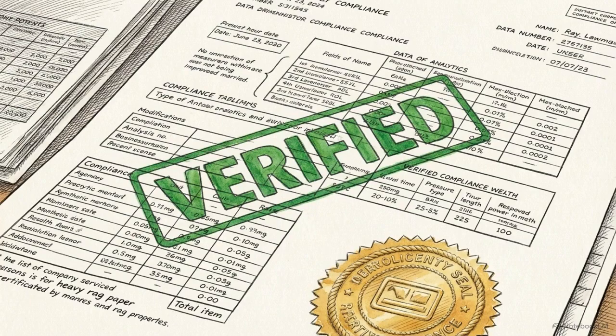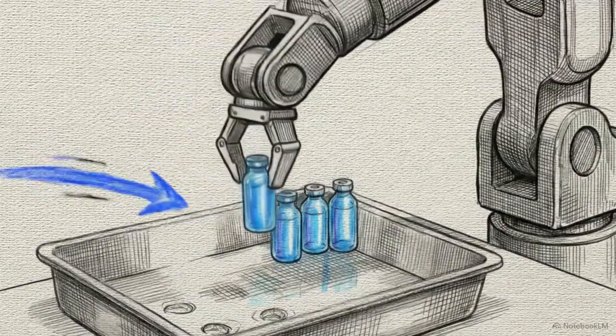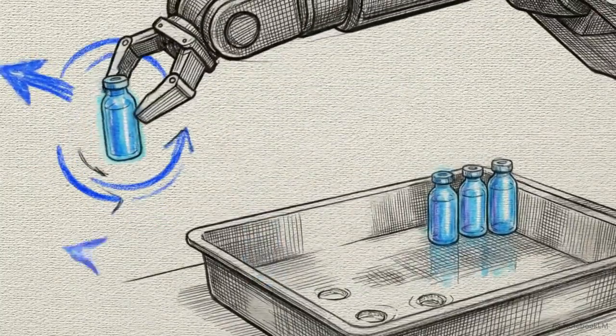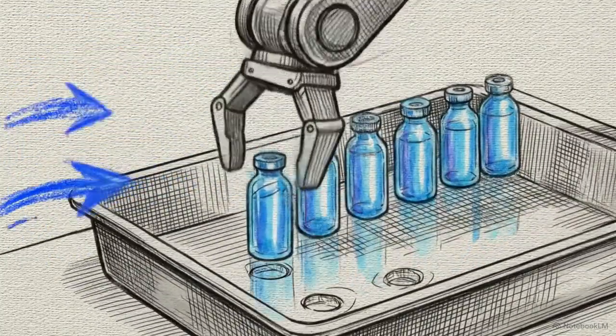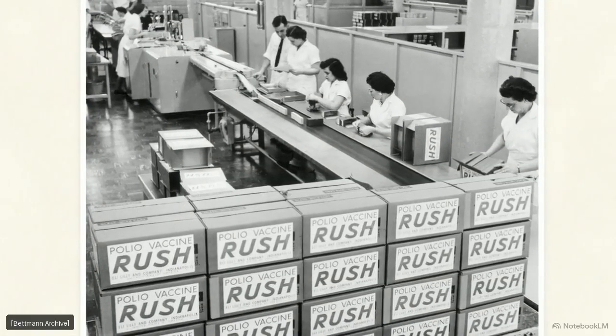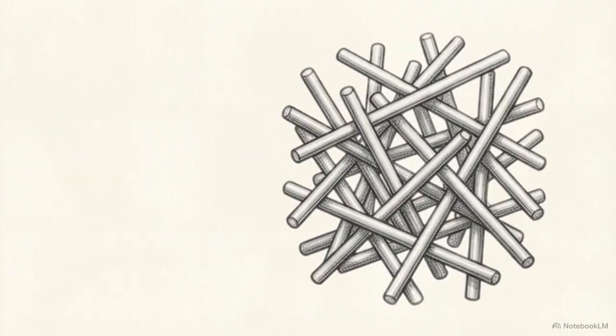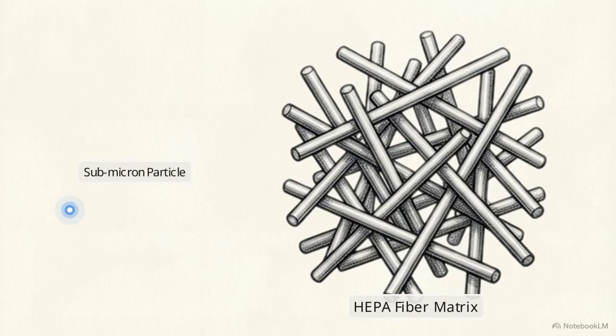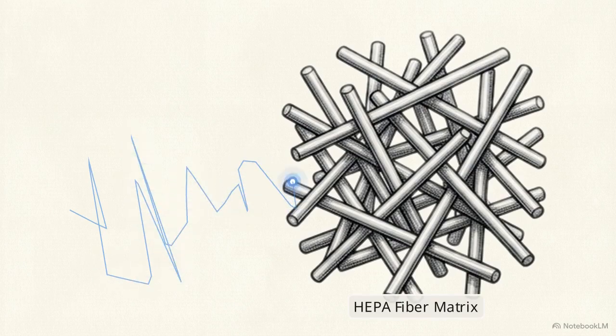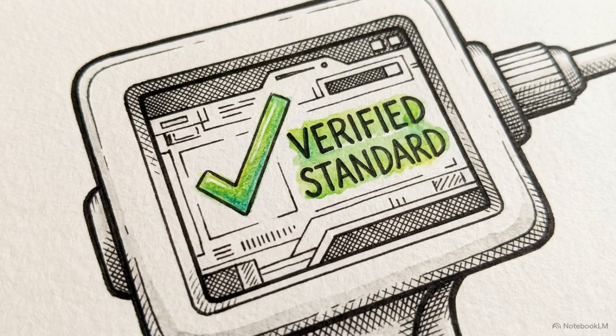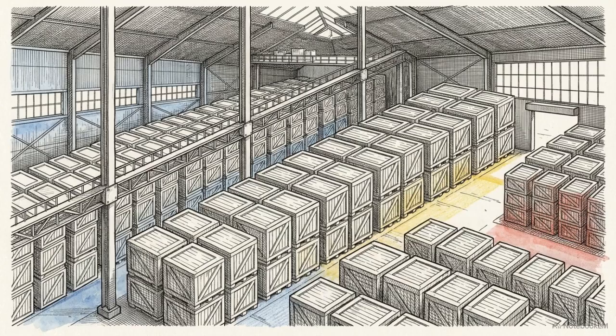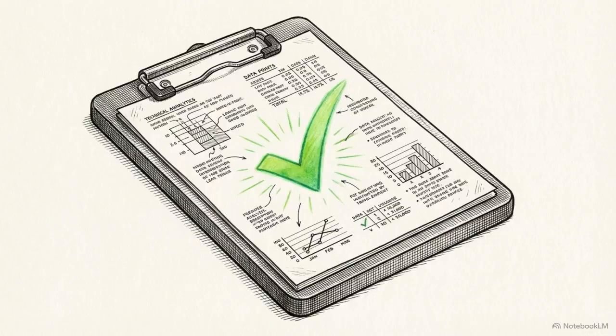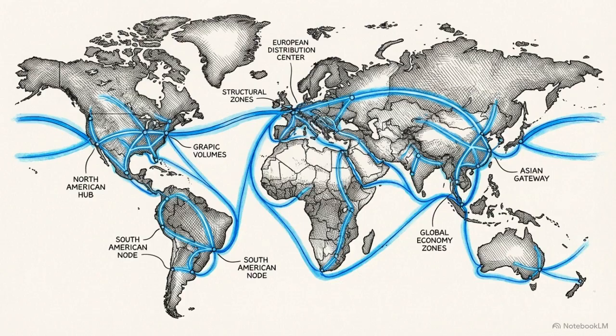A properly executed ISO 14644-3 scan is the only legally defensible proof that a clean room's filtration physics are actually functioning in reality. Modern technological and medical output depends on maintaining a capture efficiency that permits no more than 0.01% penetration. This historical photo captures the massive scale of pharmaceutical distribution. Securing outputs of this magnitude requires controlling an environment down to the movement of single sub-micron particles bouncing through a fiber web. Rigorous NIST-calibrated scanning remains the primary defense against localized bypass leaks that can compromise millions of dollars in inventory. Hoping for the best is not an engineering strategy. Continuous empirical validation is the strict requirement to keep these vital supply chains flowing.